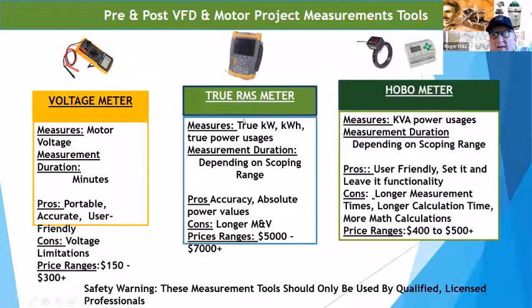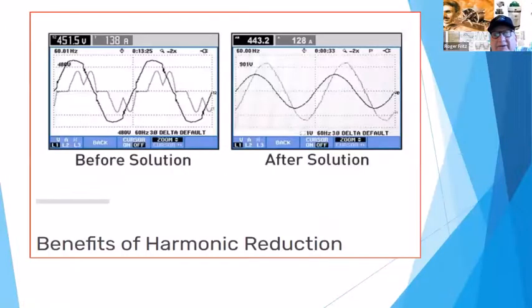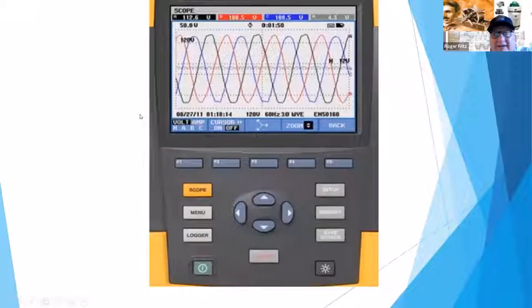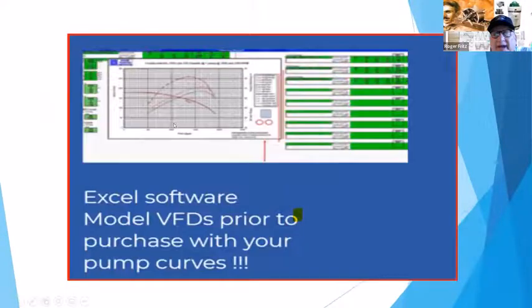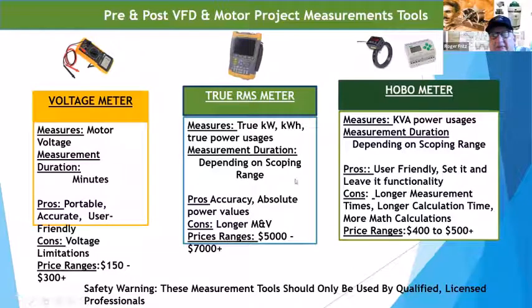And then you've got true RMS metering, which means you're calculating the true power equivalent from all those various harmonic contents and details, because a lot of the straight meters out there, with an amp meter or a voltage meter, you don't gain any of this ripple. You don't see it. So it's important that you ultimately have true RMS metering to determine where your real load factors are.